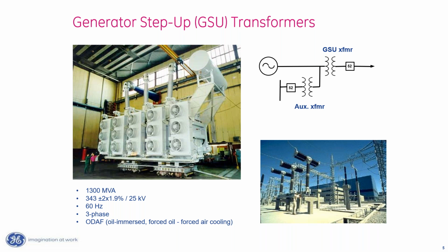So if we have a ground fault out on that transmission line from something like a great blue heron or some other large bird that can span the conductor, or not the conductor, but the insulator, and can cause a phase-to-ground fault, that transformer will block that zero sequence current, and we won't see that on the generator, which means we don't have to coordinate with the ground elements out on the transmission system. It also means that we're protecting our generators from those zero sequence currents. We will still see the negative sequence current, but not the zero sequence.